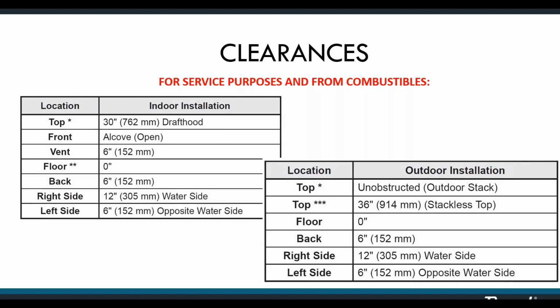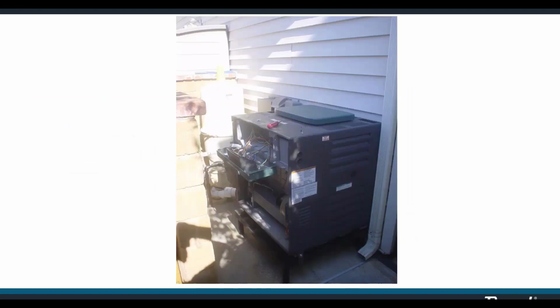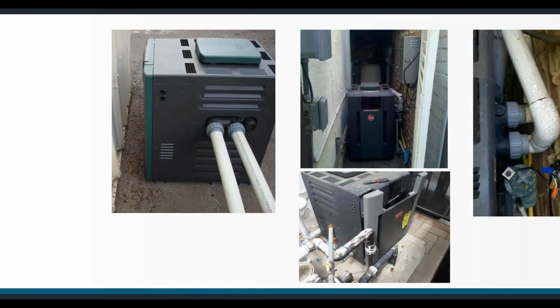On the water side, for instance, you could use more than 12 inches if you can get it. The front of the heater needs at least 24 inches just to get the burner tray out. And again, more if you can. Remember, the front of the heater is where you're operating the heater. Failure to maintain clearances makes the heater difficult to work on and can certainly cause damage to other nearby surfaces.